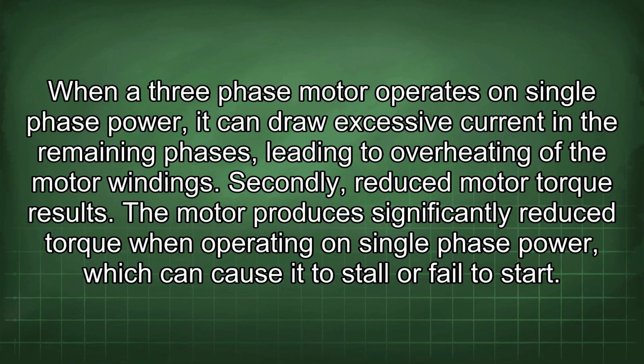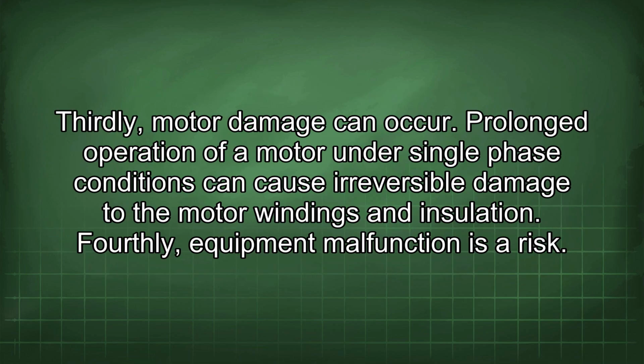Secondly, reduced motor torque results. The motor produces significantly reduced torque when operating on single-phase power, which can cause it to stall or fail to start. Thirdly, motor damage can occur. Prolonged operation of a motor under single-phase conditions can cause irreversible damage to the motor windings and insulation.